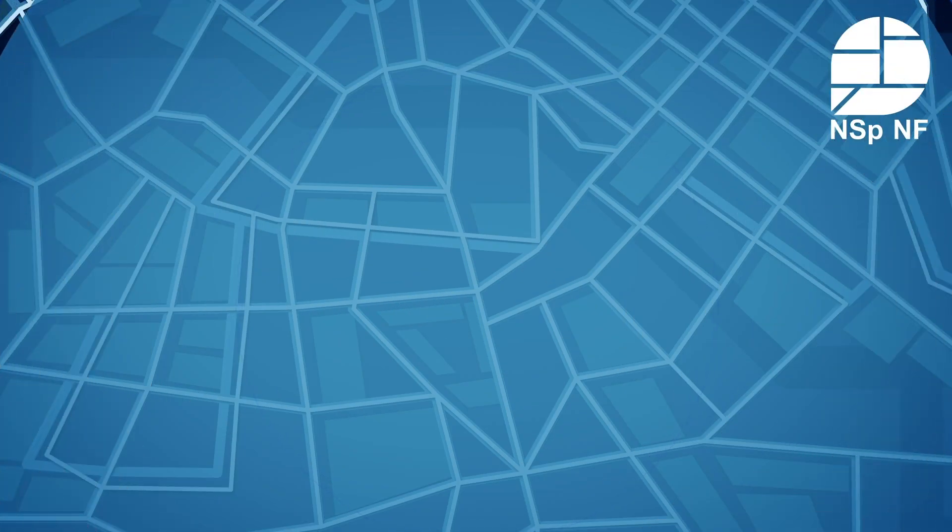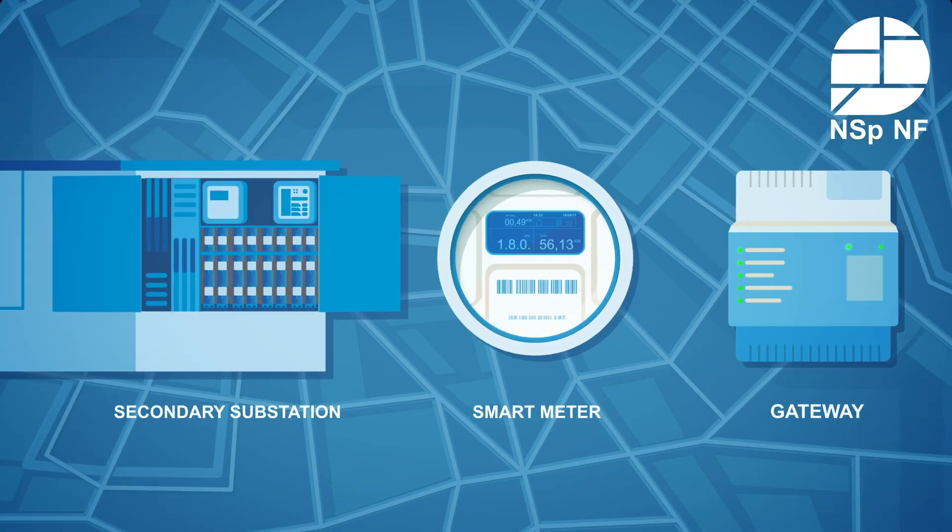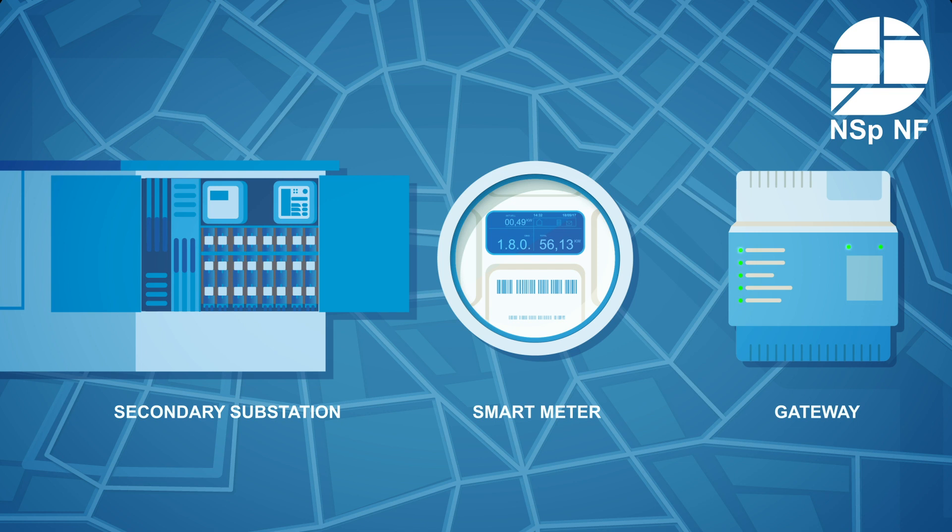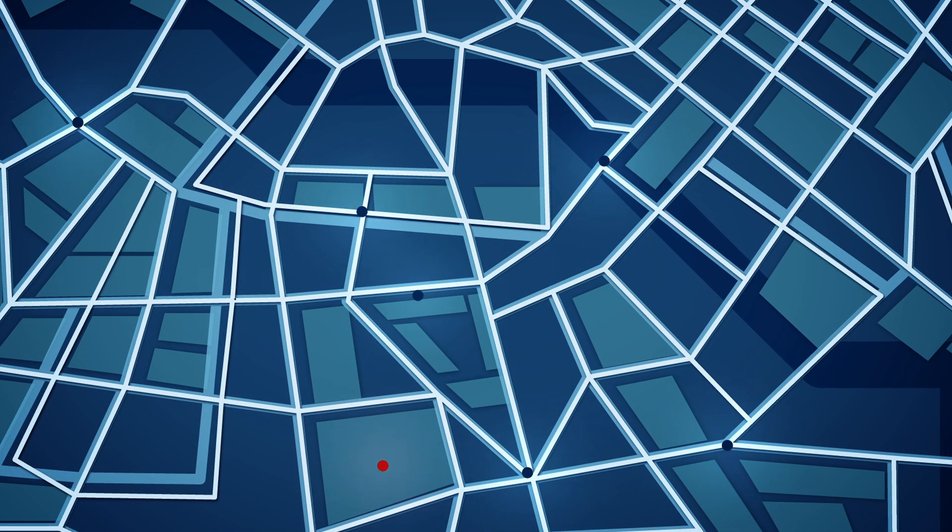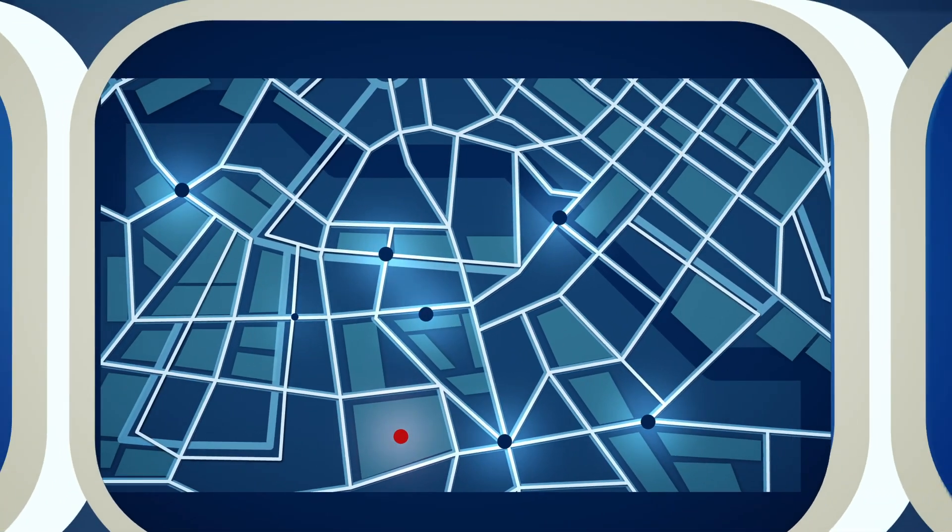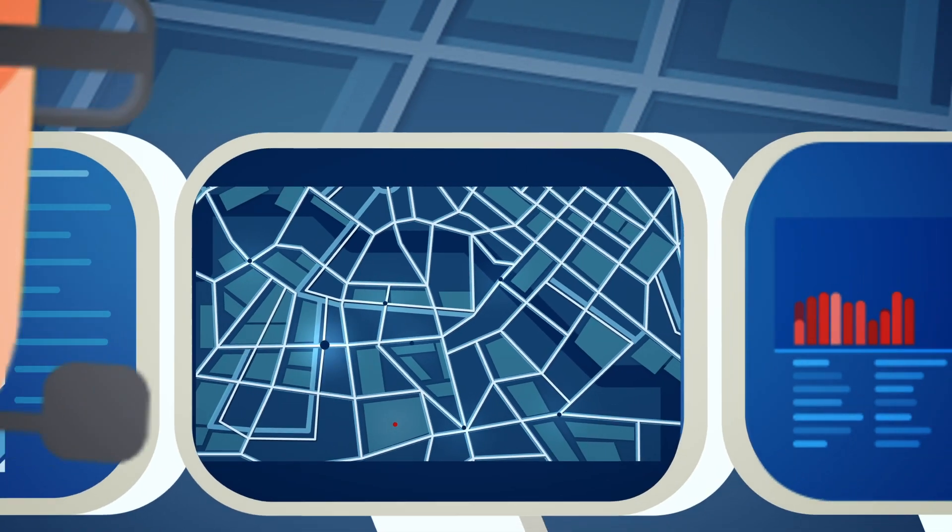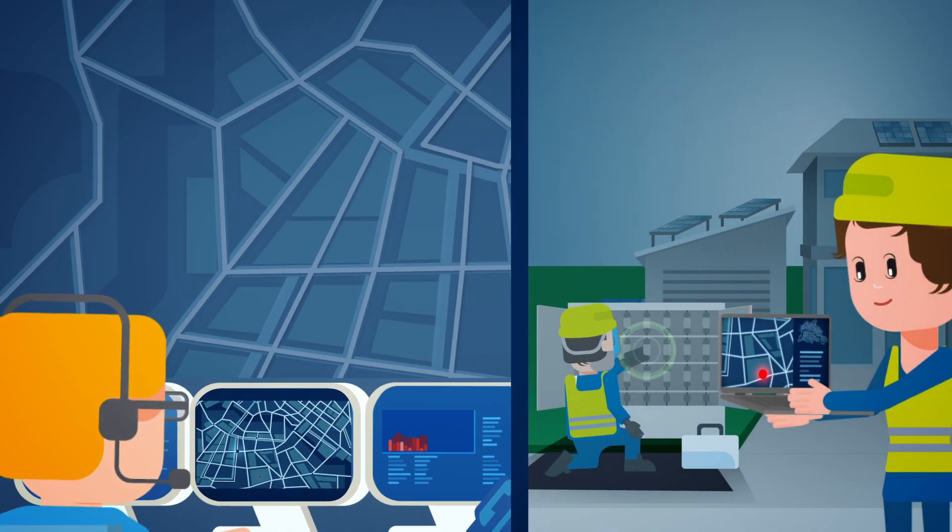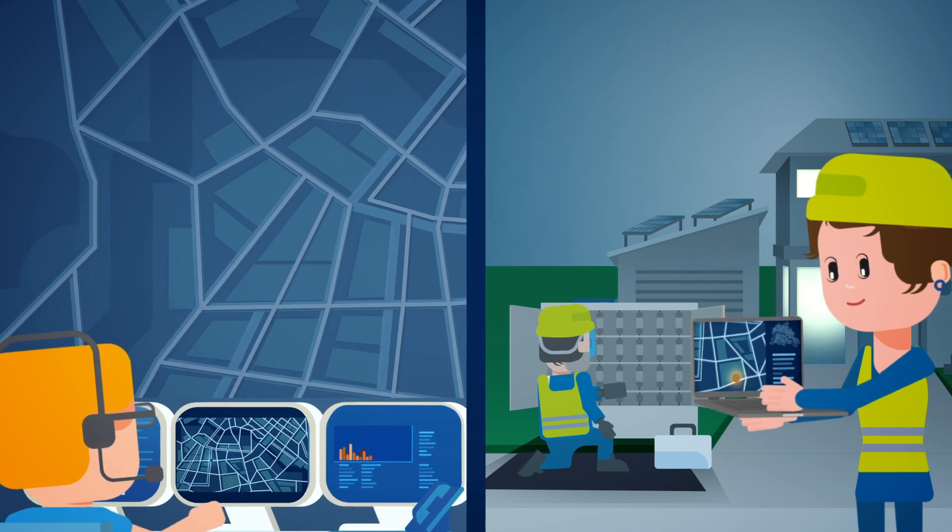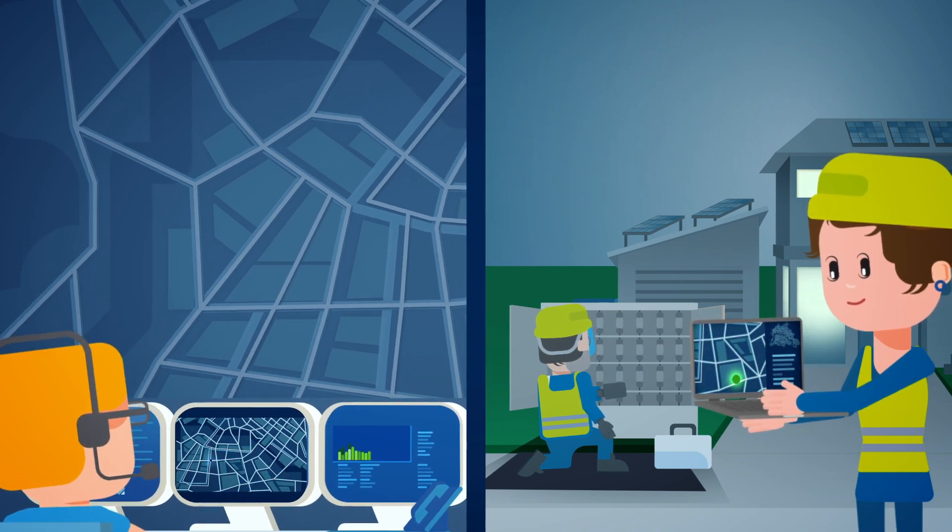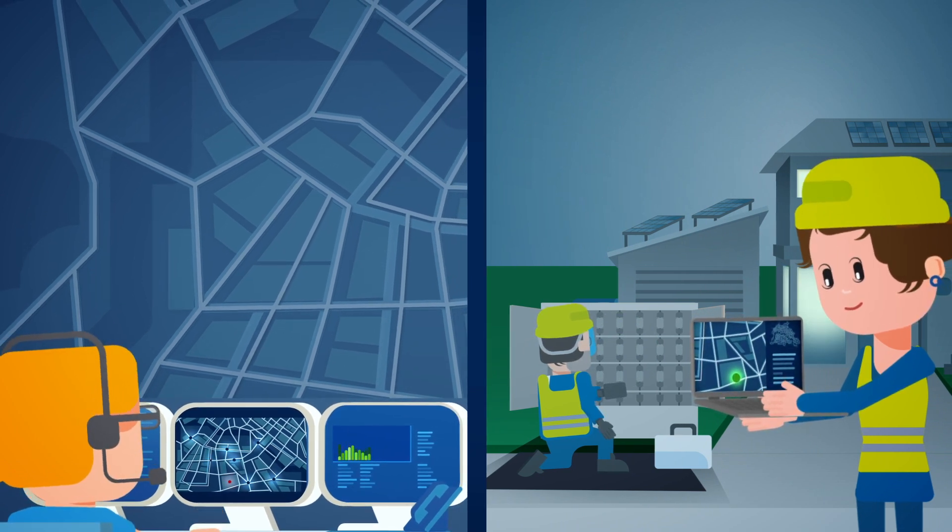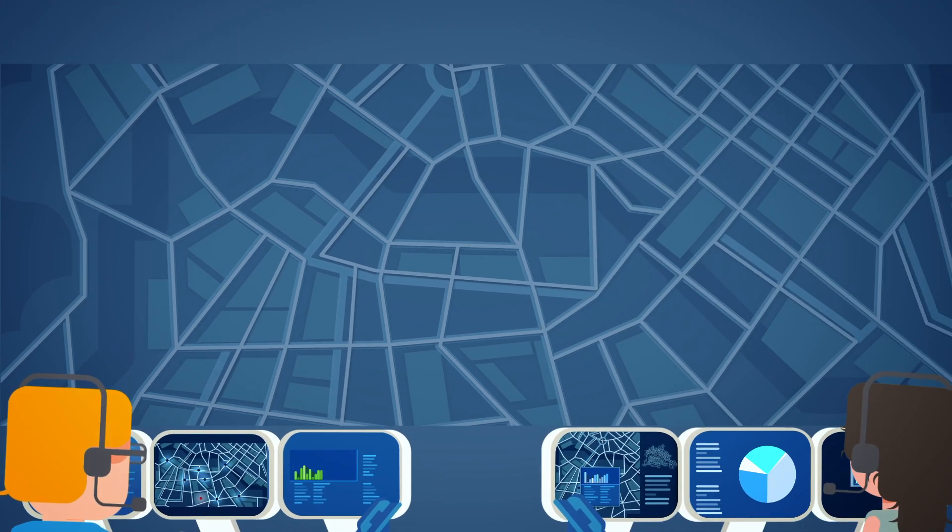For the new centralized low voltage grid management, the integration of Berlin-wide gathered 1KV network data creates a clearly observable network infrastructure. Based on the innovative features of the ADMS, we modernize our processes to enable a close collaboration between low voltage grid operators and on-site operations.